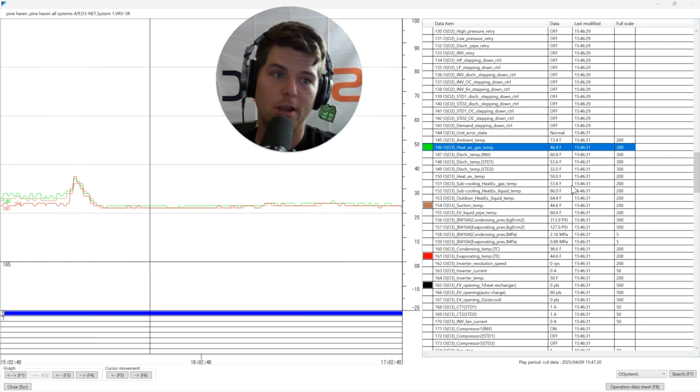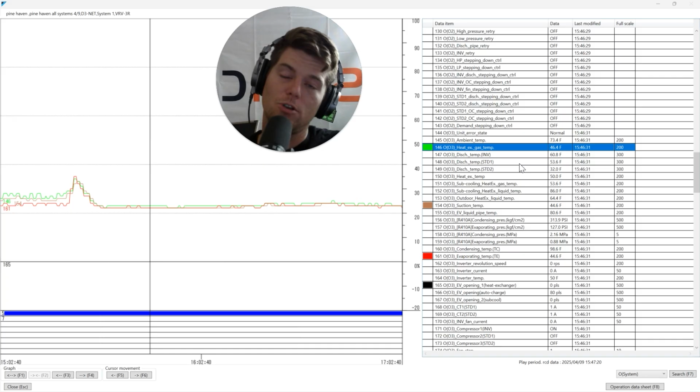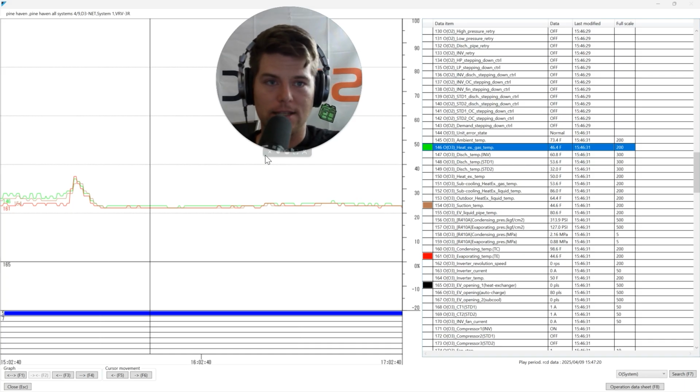So yes, this expansion valve is failed. Now, what do you do for the repair? For this repair, you're going to want to go through and replace all 3 expansion valves on the outdoor units, because if one is dead and bleeding by, you could have the same scenario with another module right next to it. And these are old systems, and so I would just go through and I would do that. I would also recommend the compressor cleanup kits on this system, because these units, they don't like contamination, man.